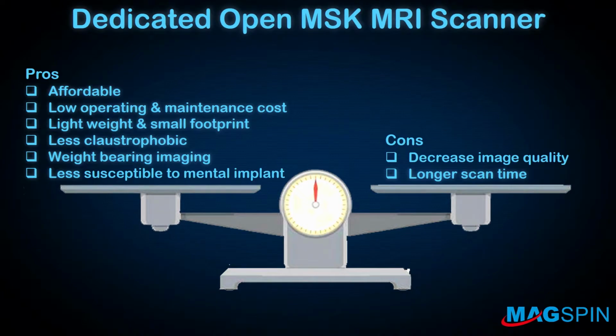Right now, the trend is either to go really high field or to do something at low field, and we've been constantly trying to balance the pros and cons of these systems. For this system, the pros are that it's affordable, has really low operating and maintenance costs since you can just switch it off at night, it's lightweight, less claustrophobic for most patients, allows possible weight-bearing imaging, and is less susceptible to metal implants. However, the cons are that image quality decreases and scan time is longer.